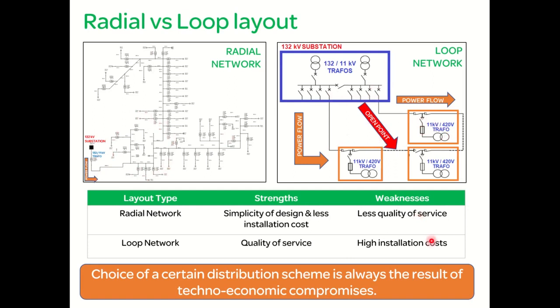We can now discuss the merits and demerits of radial and loop structures. The strength of radial network is simplicity of design and less installation cost due to its single feeder structure and fewer electrical components; however, it can easily face blackouts, which is why it lacks reliability. On the other hand, the loop network provides more reliability and continuity of supply due to its double power-feeding structure, but installation cost is higher due to double distribution lines and additional electrical components such as changeover switches. The choice of distribution scheme is always a techno-economic compromise.